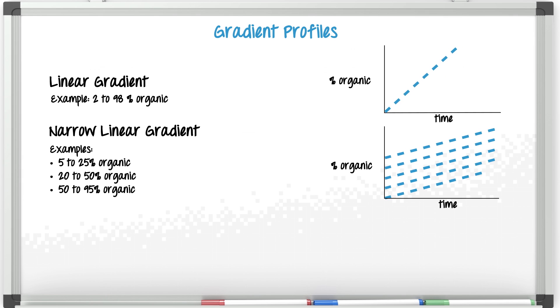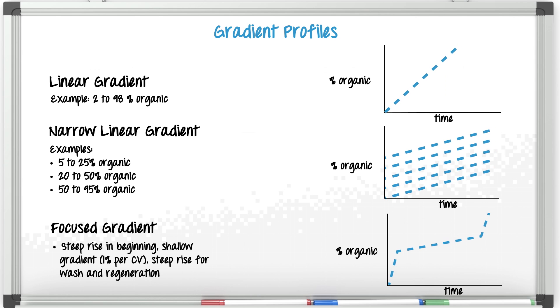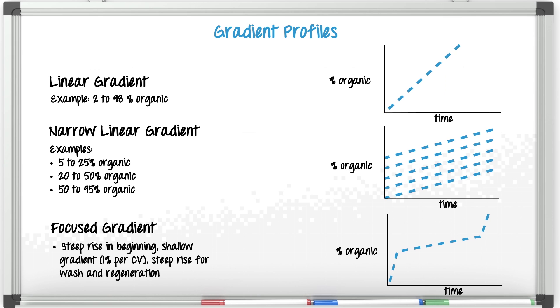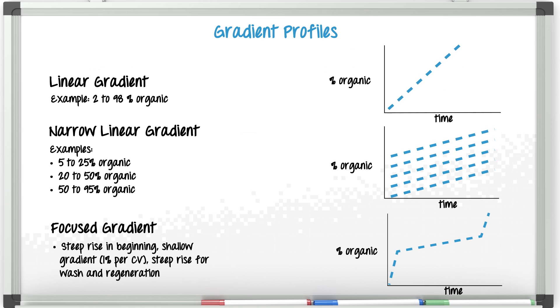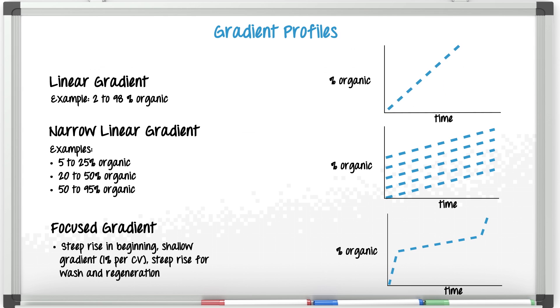The trick is to get this shorter. In example two, this is a set of narrower linear gradients where we start off at higher organic. Alternatively, we can use a focused gradient. The gradient starts at the same low percentage as in our traditional linear gradient, however the first segment has a steep rise. Next, the shallow gradient segment is defined by the elution percentage of our target compound, and the final segment ramps up quickly to the final organic percentage of the original method.